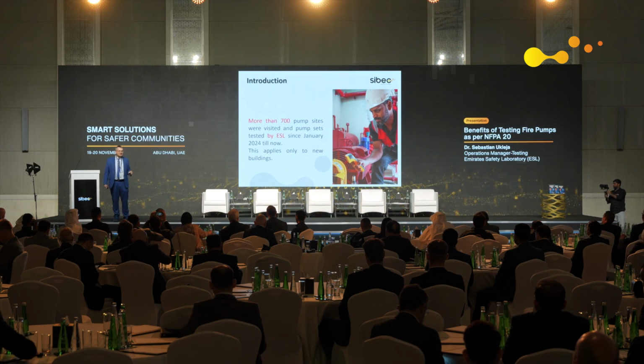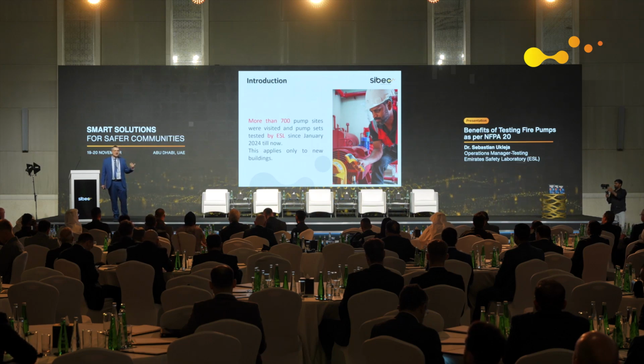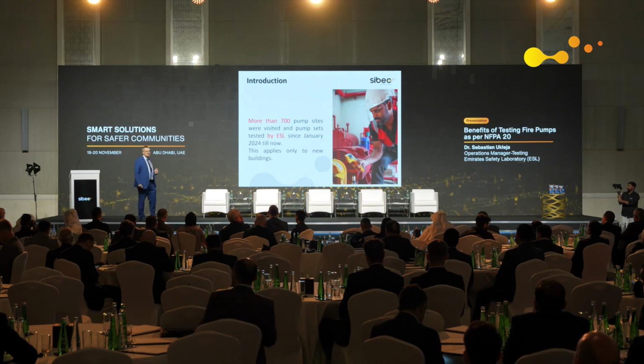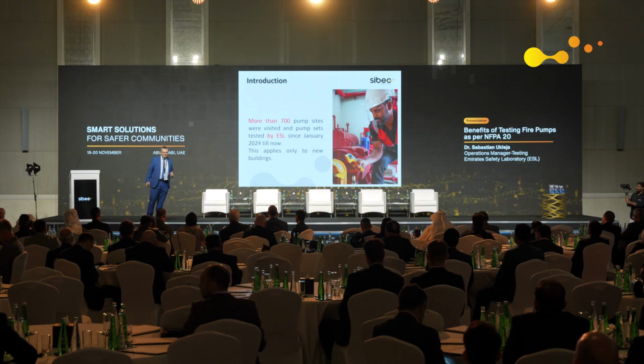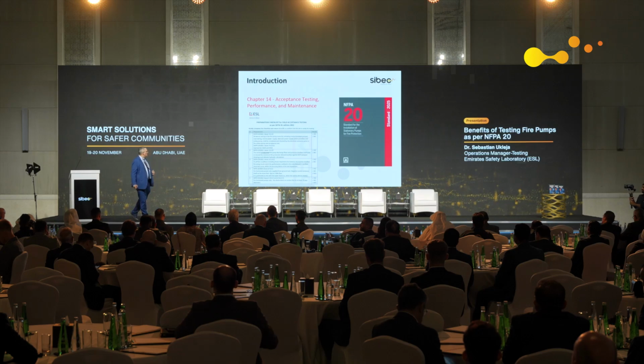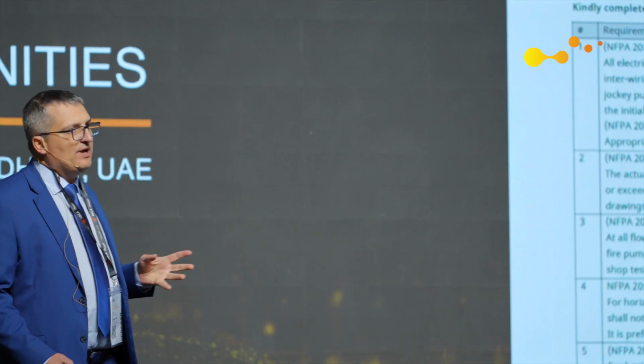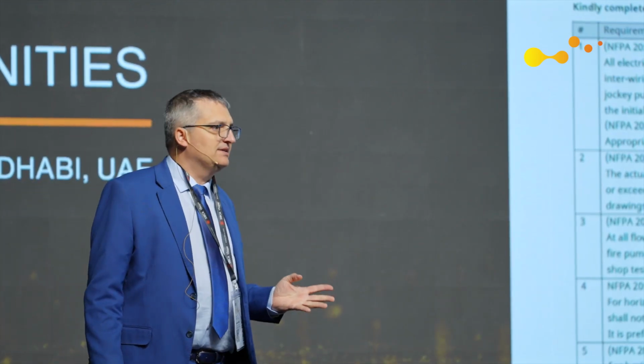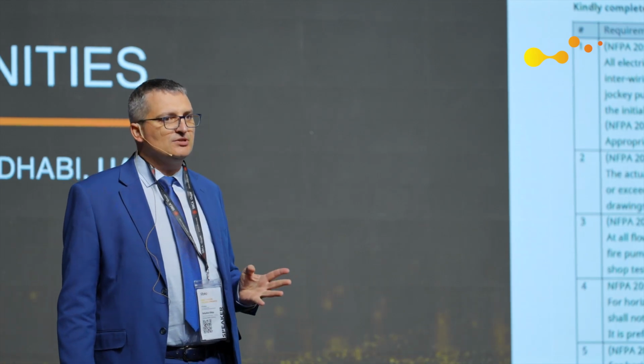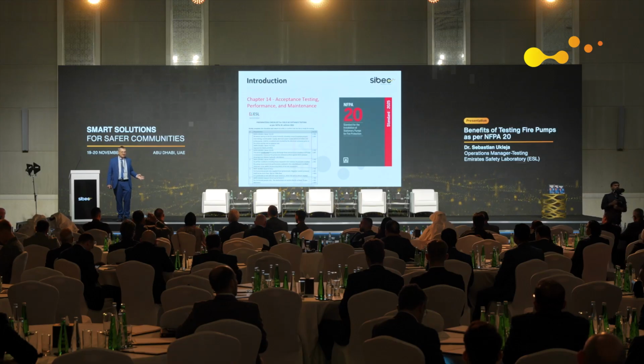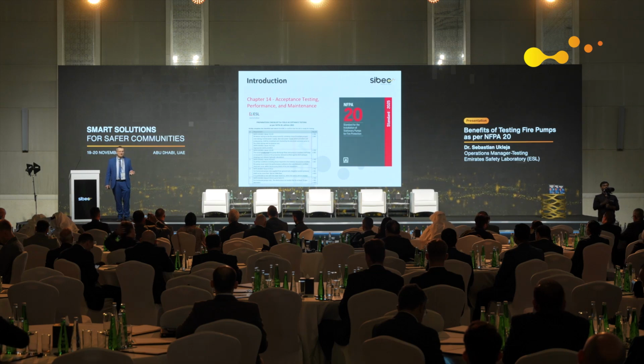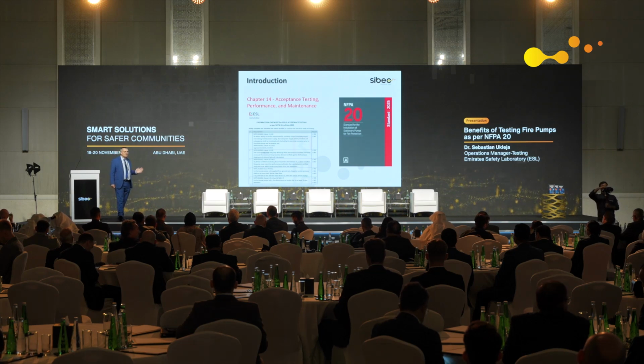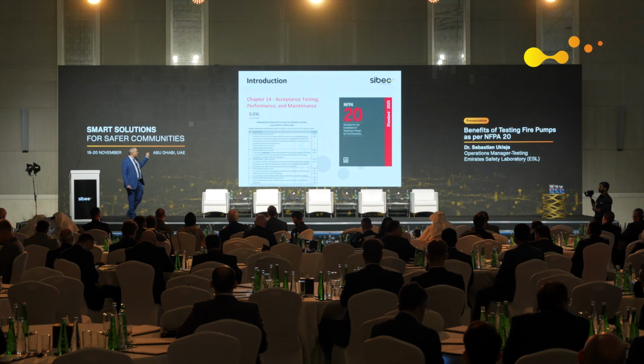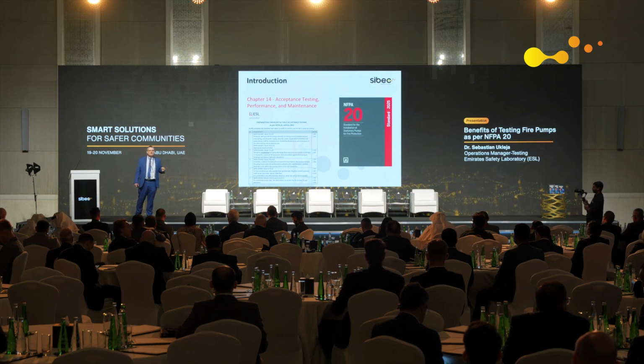I'm not even touching on annual maintenance or annual testing - I'm talking today only about initial testing, let's call it acceptance testing. We prepared a checklist because we discovered that some contractors don't know NFPA 20, even though they should - it's a requirement of the UAE code, but they don't know it. So we prepared a checklist showing a step-by-step guide of what will be checked by us during initial testing.